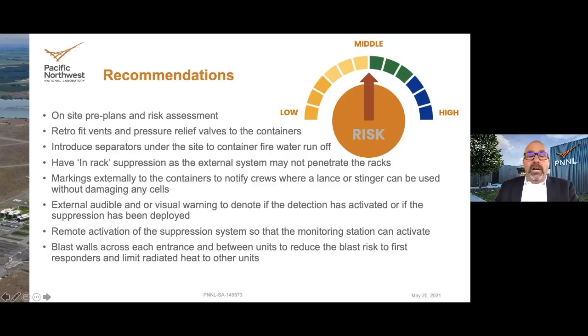External markings on the containers to notify crews where a lance or stinger, also referred to as a piercing nozzle, can be used without damaging the cells. My personal opinion is you might be a little too close if you're taking those kinds of actions there. This equipment is really written off by the system owner; they're not going to be brushing off the carbon soot and turning it back on. So the real goal is life safety and preventing extension to other units.